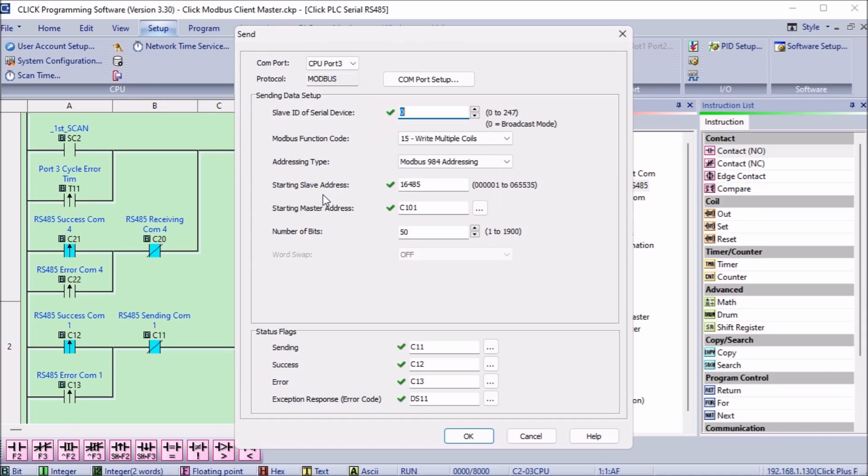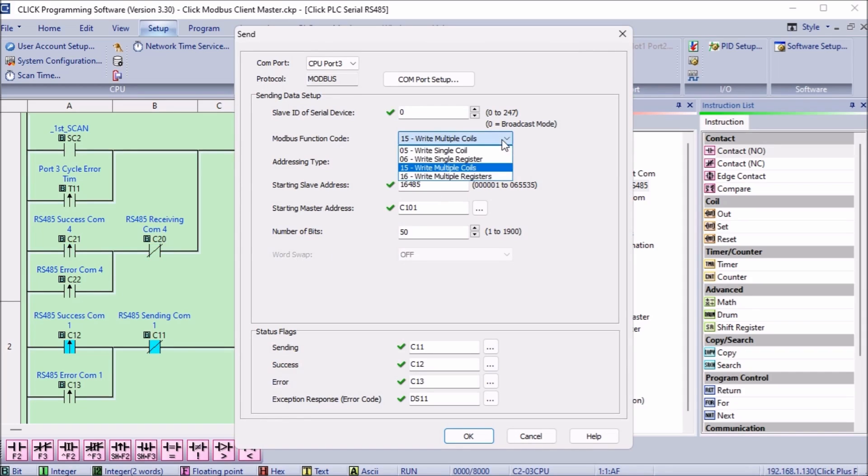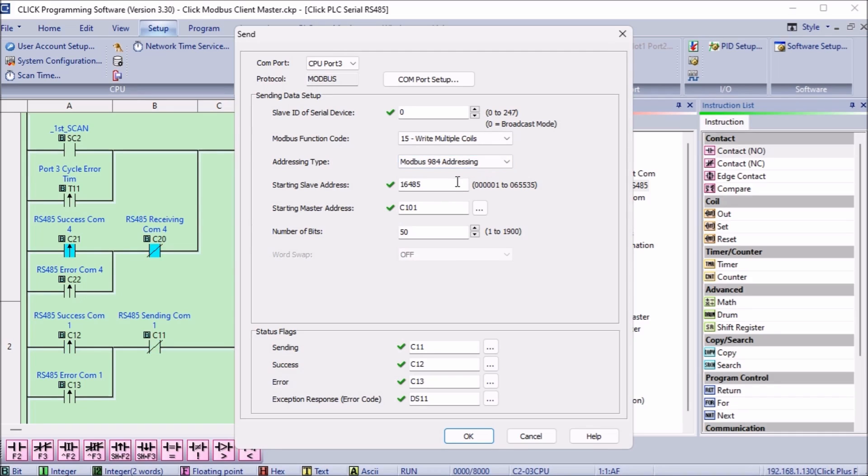Double click on the send instruction and we can look at this in more detail. The Modbus function code is set for 15. This is used to write multiple coils. Our addressing type is set for Modbus 984 addressing and the starting slave address is 16485. The starting master address is C101.